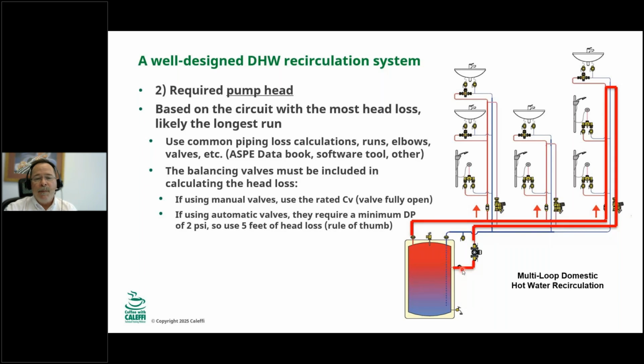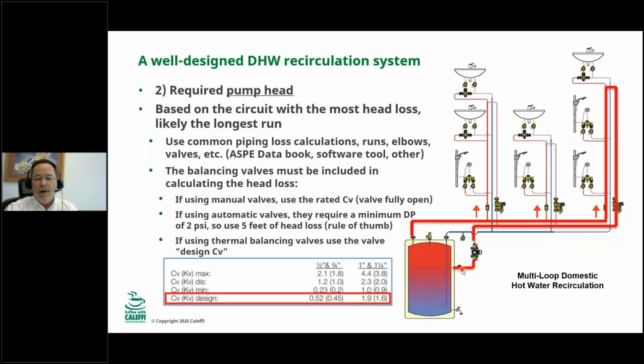The new thermal balancing valves are a little bit different. You have to look at the manufacturer's literature and look for the design CV. You don't use the maximum CV because they almost never operate at maximum or full open. Thermostatic balancing valves modulate from almost closed to about 10 degrees Fahrenheit when they're open. So that's the range they work in. And most manufacturers have a design CV. That's the CV you'll use to determine the head loss for those.